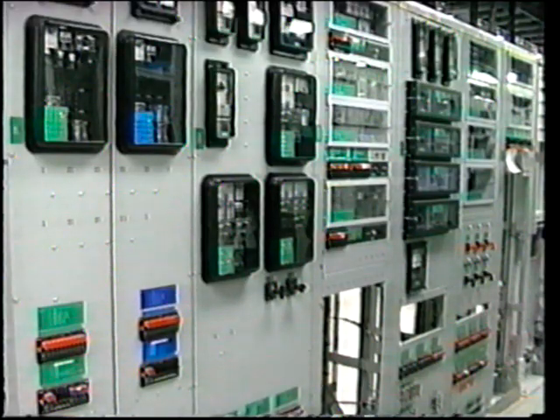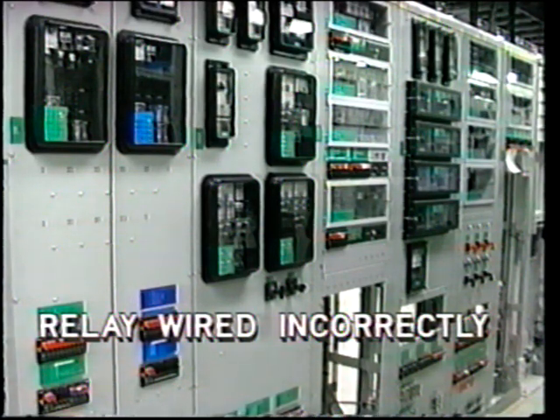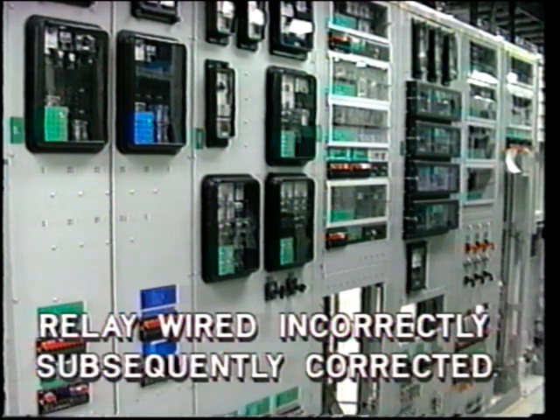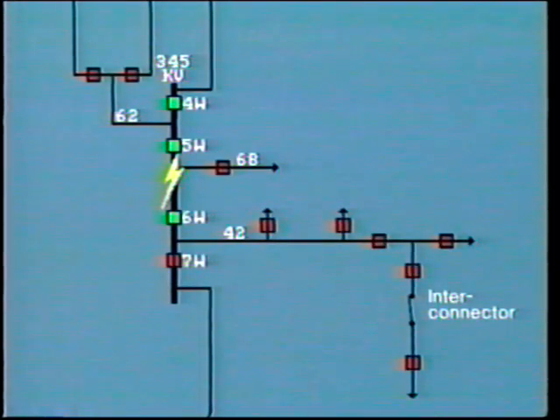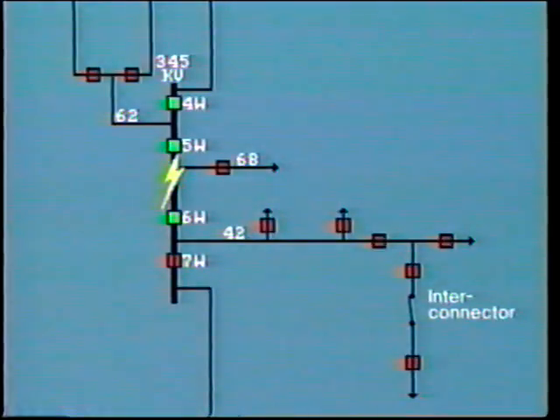Subsequent investigation proved that one of the relays in the circuit had been wired incorrectly. Once again, an error that apparently slipped through the commissioning tests. The wiring was subsequently corrected and the relay placed back in service. But this was not the only problem during this fault incident. When a fault occurs at any point, it is detected by other protection schemes throughout the system. However, as we know, the protection schemes are coordinated to provide selectivity so that only the faulty section is cleared. Unfortunately, this did not happen in this case.